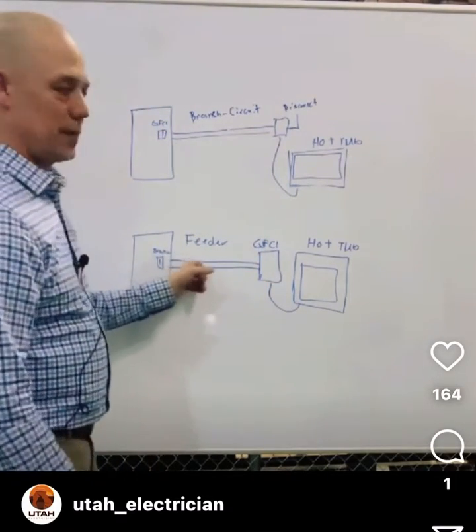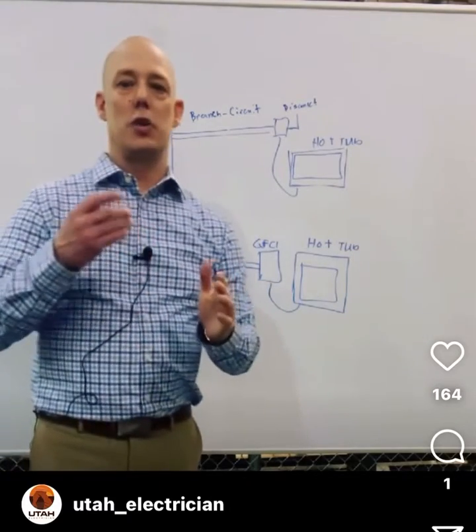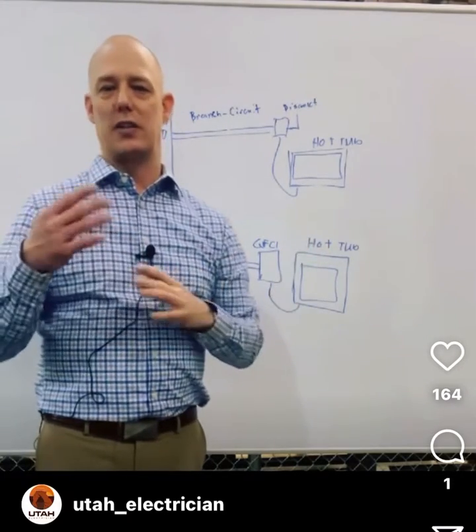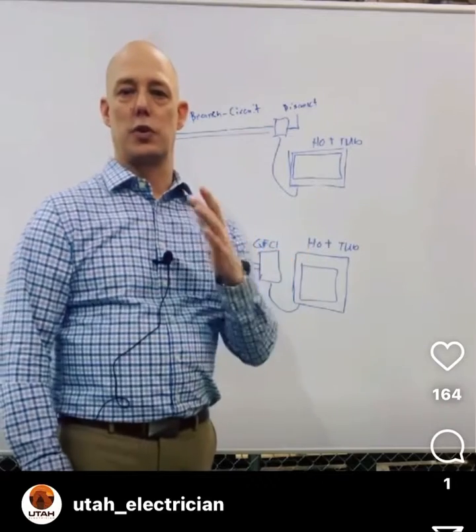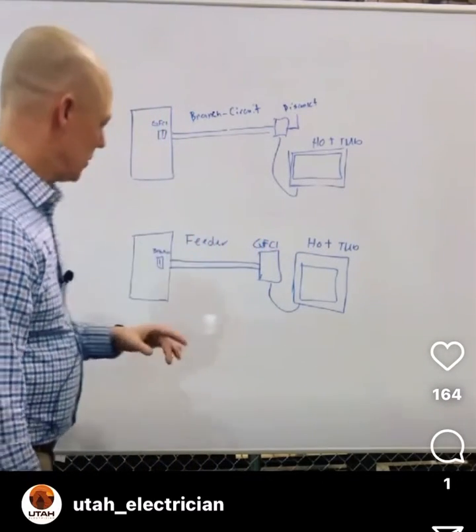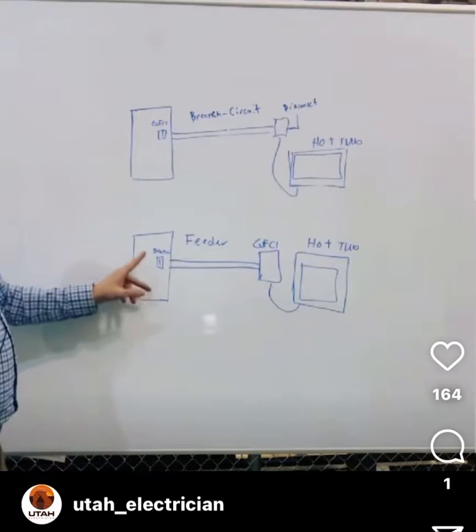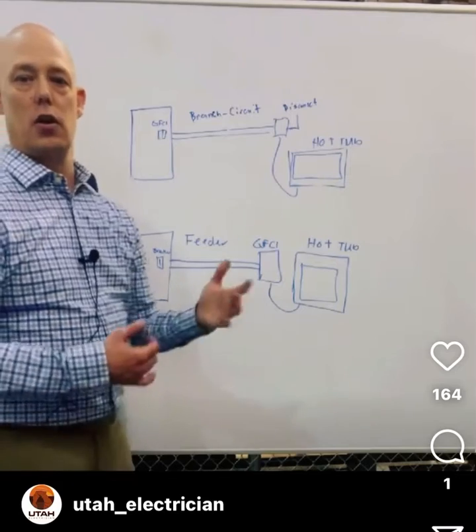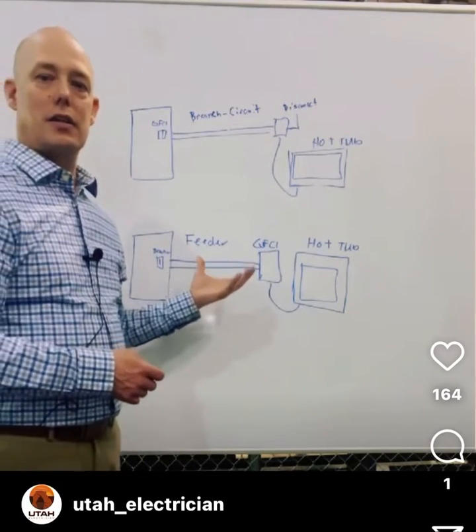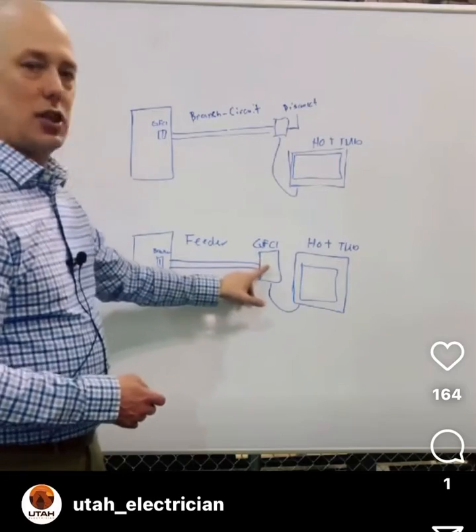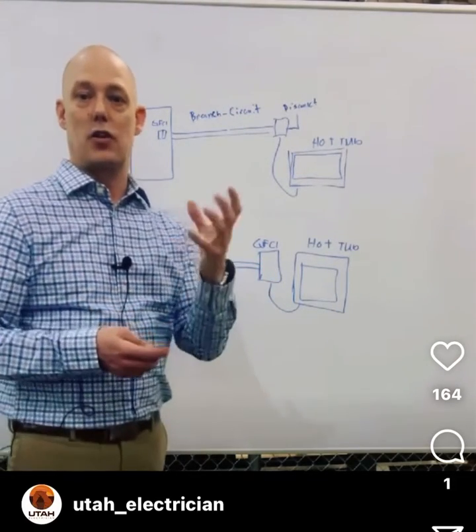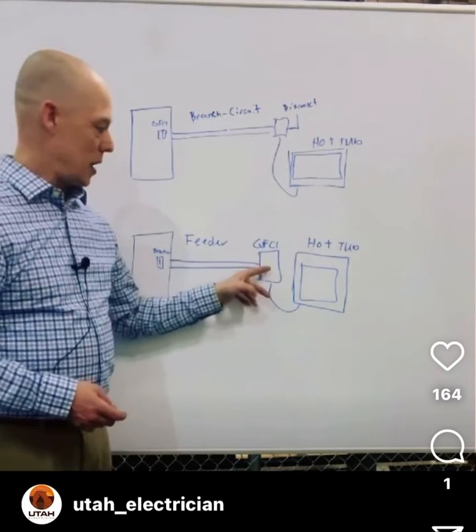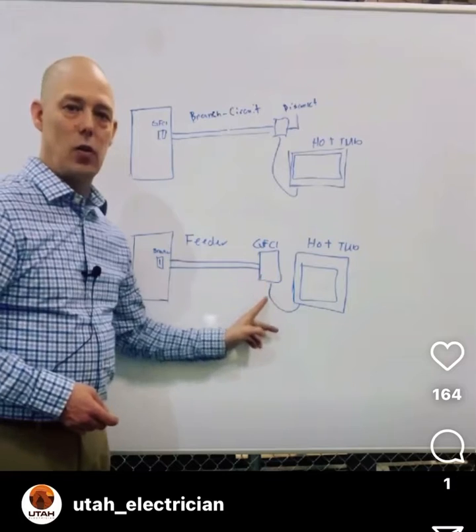Now down here, this becomes a feeder because a feeder is between my panel and my final overcurrent protection device — and there's some other stuff in Article 100 when it comes to feeders with separately derived systems, I would check that out. We've got a breaker that's not GFI protected that now feeds a spa disconnect. You can go to your local hardware store and buy a disconnect or a spa disconnect that has GFI protection. That disconnect, GFI protected, is also your last overcurrent protection device.